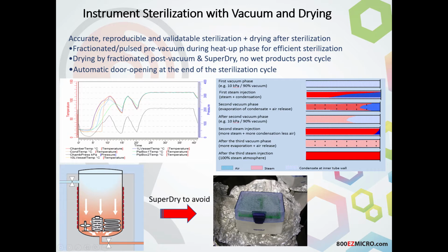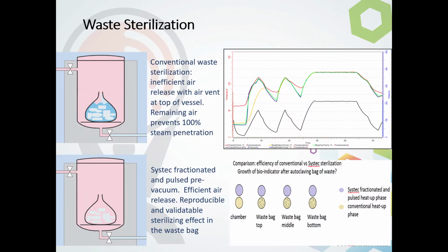You can imagine, and I'm sure most of the folks on here have seen, pipette tip boxes that come out that look like this, completely wet. How are we going to keep that sterile without putting that in a hood and allowing it to dry overnight, however long, before we're actually able to use those pipette tips? With our SuperDry option, we're going to be able to completely dry that. Once the cycle is done, we can have the lid automatically open. Then you can come and remove the contents when you see fit. So that's how we would approach instrument sterilization.